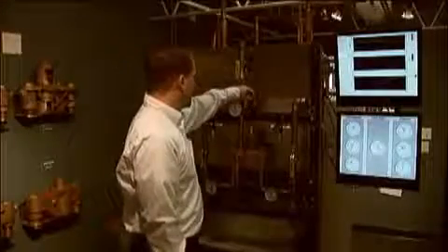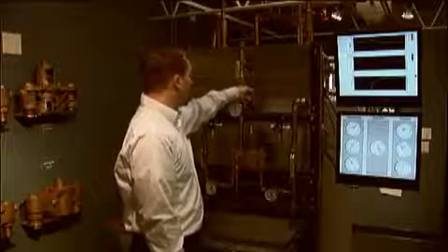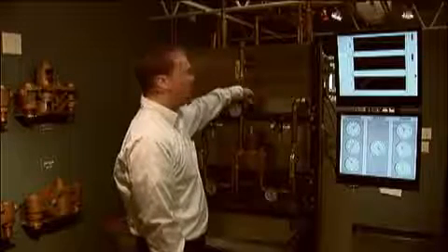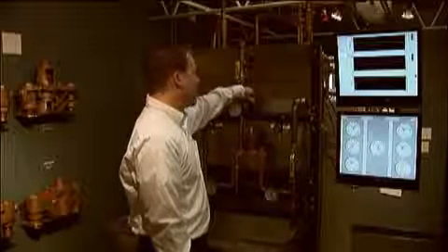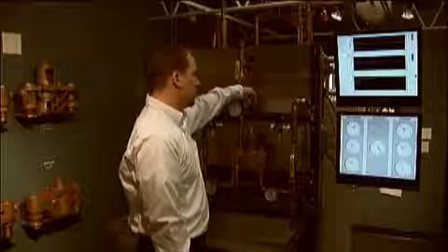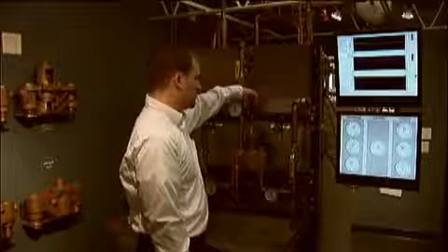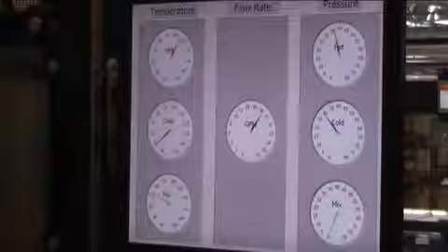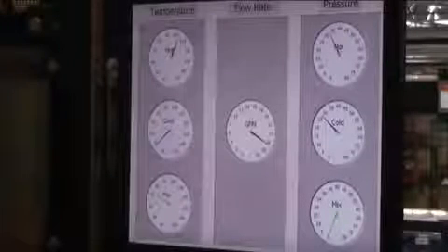To change temperature in a mixing valve is very easy, just with a common tool. Through the top, 5/16" Allen wrench. If I turn in a clockwise direction, I will get a cooler setting. If I turn in a counterclockwise direction, I will increase the temperature.